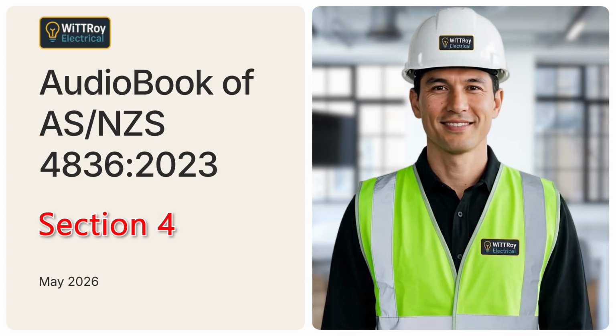Clause 4.1, General. Clause 4.1 explains that each hazard presents its own type and level of risk. The controls used for one job may not be enough for another job. Before work starts, several factors should be considered. This includes the equipment being installed, the environment where the electrical equipment will be installed, energy storage systems, building materials, and earthed situations. In simple terms, safety is not only about the circuit, it is also about the place where the work is done. For example, the same electrical task may become more dangerous if the area is damp, cramped, poorly lit, near earthed metalwork, or close to other live parts. So the controls must be chosen for the actual job, not just copied from a previous job.